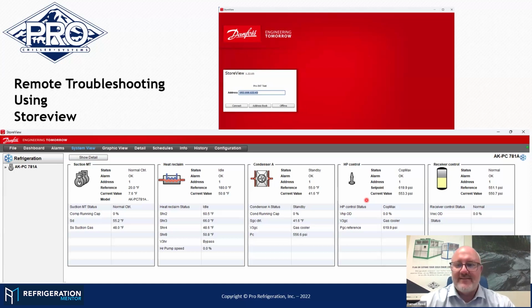So that's expected. Receiver control, my reference is 550. My current value is 550. My receiver OD, that's the flash gas bypass valve output, is at 0%. It's because my receiver's at set point. I'm not generating any pressure, and I'm not asking it to open up and let my receiver pressure come down. So really quick, you can take that snapshot with this view. I like that.